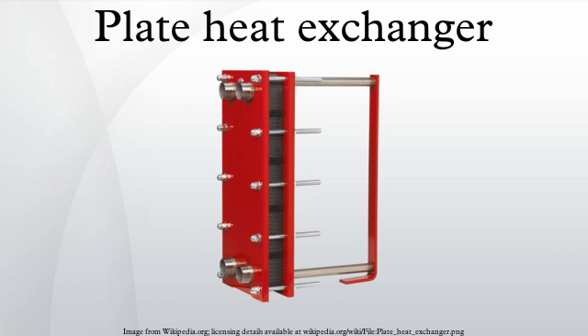These troughs are arranged so that they interlink with the other plates, which forms the channel with gaps of 1.3–1.5 mm between the plates. The plates are compressed together in a rigid frame to form an arrangement of parallel flow channels with alternating hot and cold fluids. The plates produce an extremely large surface area, which allows for the fastest possible transfer. Making each chamber thin ensures that the majority of the volume of the liquid contacts the plate, again aiding exchange. The troughs also create and maintain a turbulent flow in the liquid to maximize heat transfer in the exchanger.